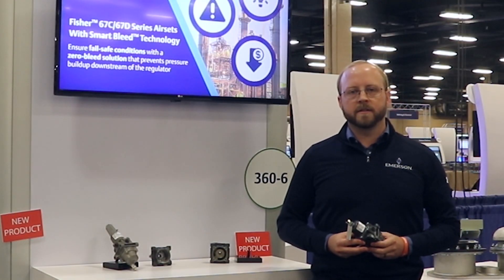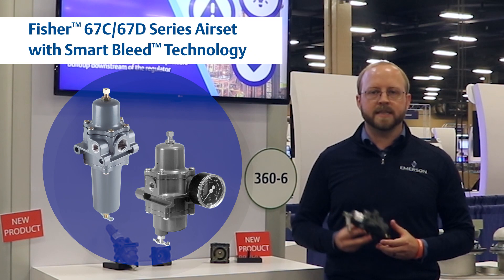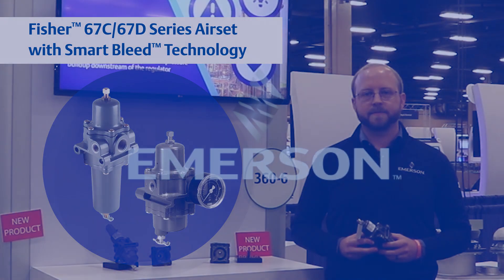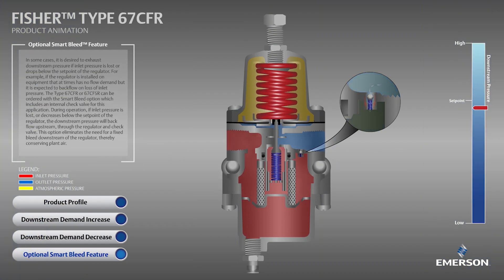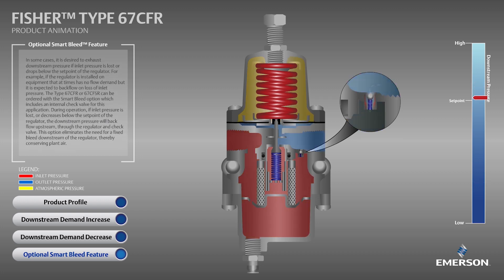The best solution for these applications is using a Fisher 67C or 67D series air set with SmartBleed technology. SmartBleed equipped air sets feature an integrated check valve that allows trapped pressure to bleed back through the regulator upon loss of inlet pressure. This feature allows you to maintain your set failure mode while eliminating the need for a fixed bleed fitting that constantly vents to the atmosphere.